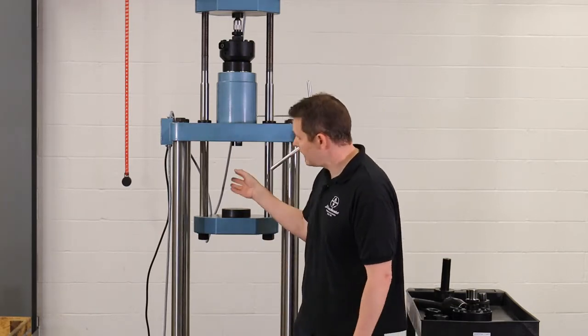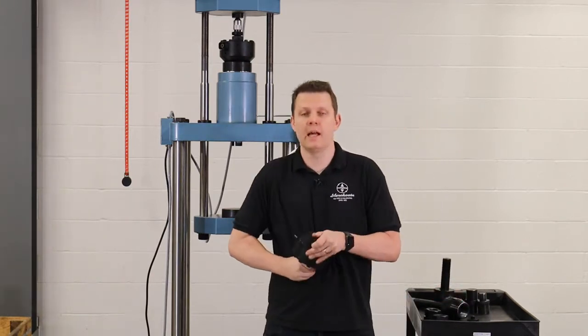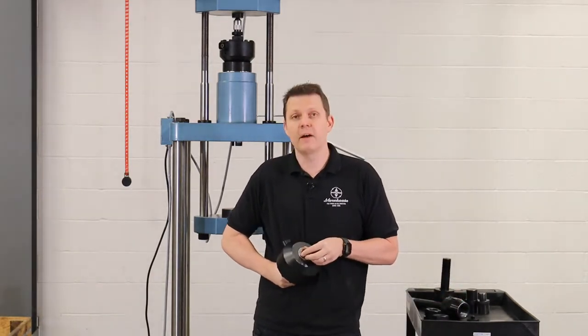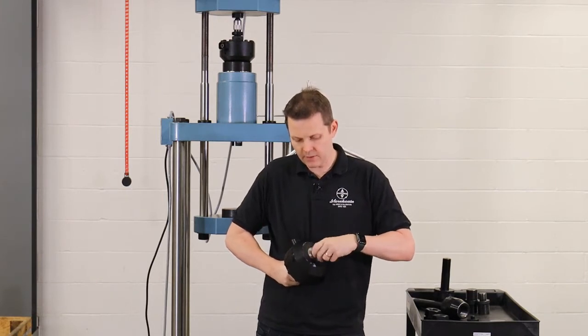Which is just as simple as sticking the load cell in the machine. However, there is one caveat: we do put in an alignment plug. This makes life a lot easier to center the load cell.